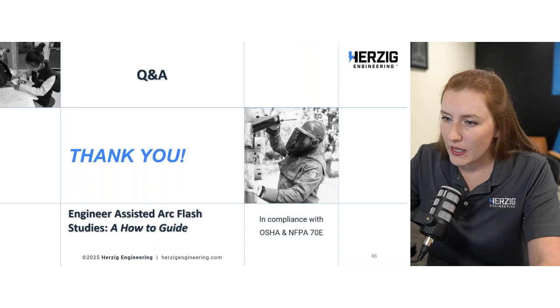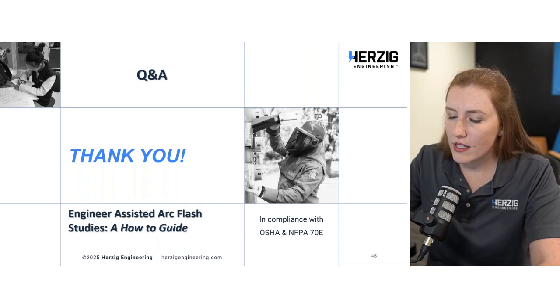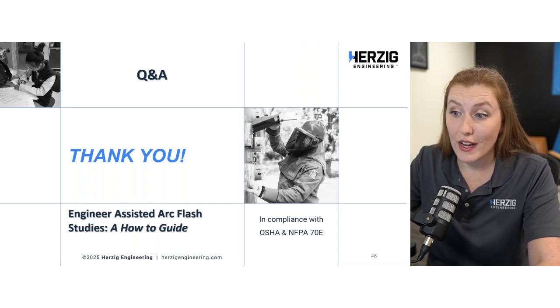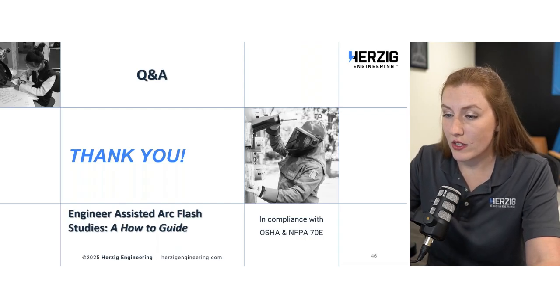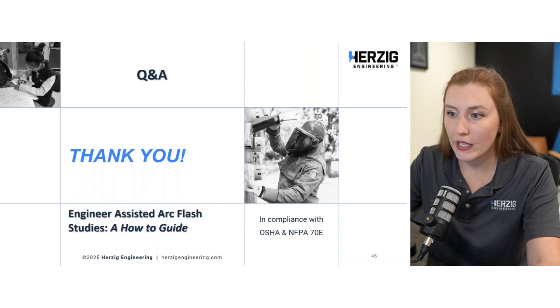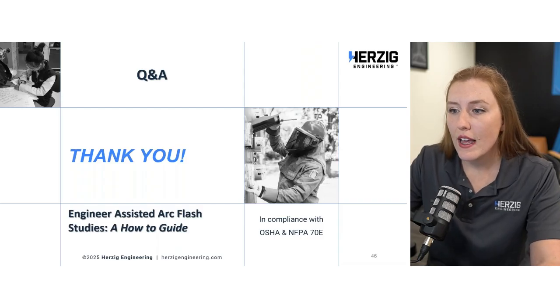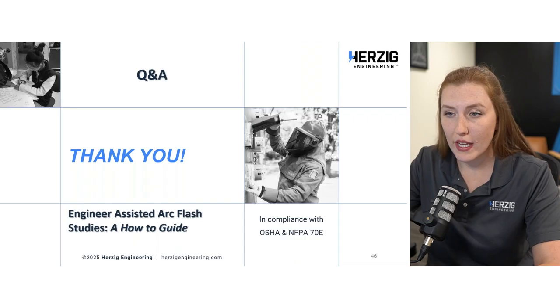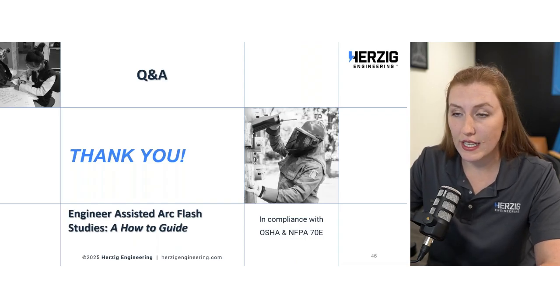All right, follow up here. So if the employer has a policy and program in place to not work on energized equipment, would they be able to argue that they don't need to have an arc flash calculation done for their equipment? No. Absolutely not, because you have to be able to verify that the equipment is off before you take off the PPE or be able to take down the boundaries.